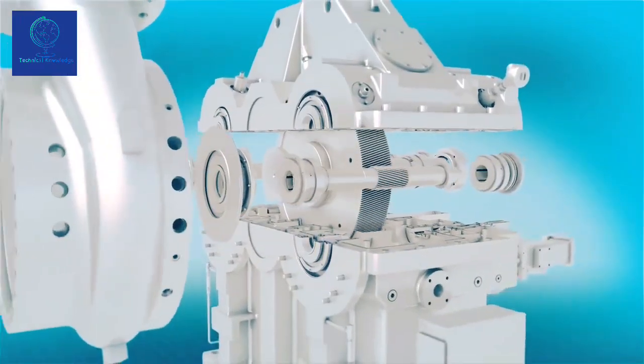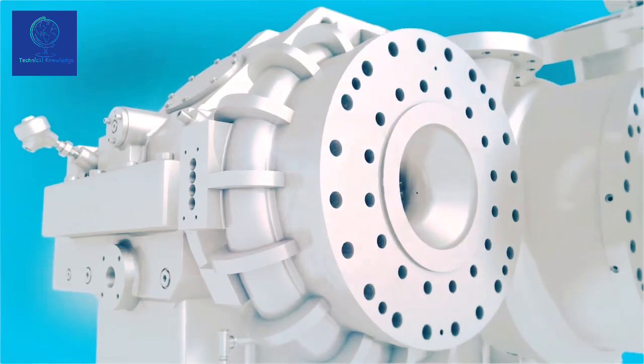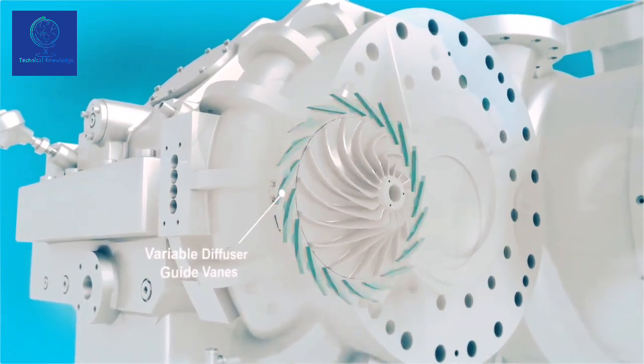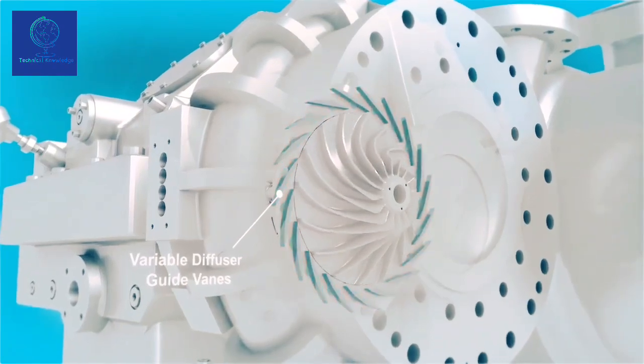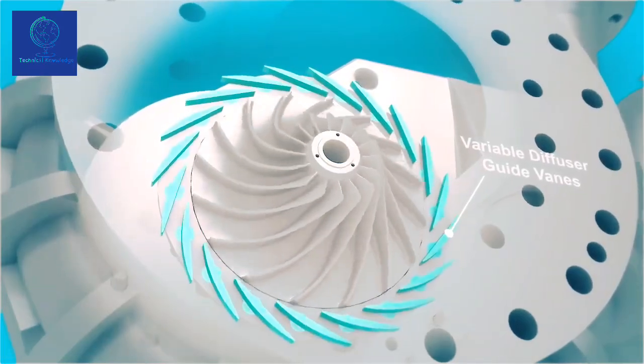To enhance performance, a number of other features are available, such as variable diffuser guide vanes, or DGVs, which can be added to complement impeller aerodynamics. Adjustable DGVs enable larger turndown, which ultimately results in wider process control without impairing efficiency, an ideal mix that is increasingly required by process designers.